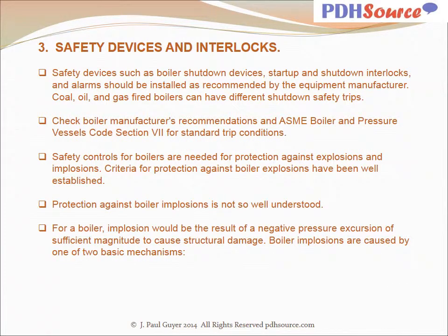With regard to safety devices and interlocks, safety devices such as boiler shutdown devices, startup and shutdown interlocks, and alarms should be installed as recommended by the equipment manufacturer. Coal, oil, and gas-fired boilers can have different shutdown safety trips. Check the boiler manufacturer's recommendations and the ASME Boiler and Pressure Vessel Code Section 7 for standard trip conditions.